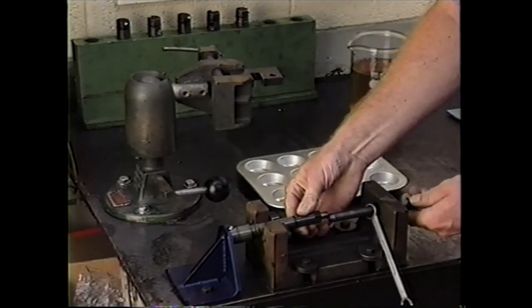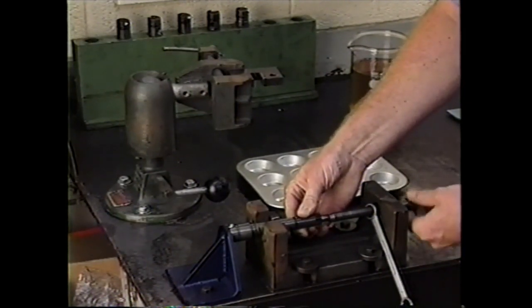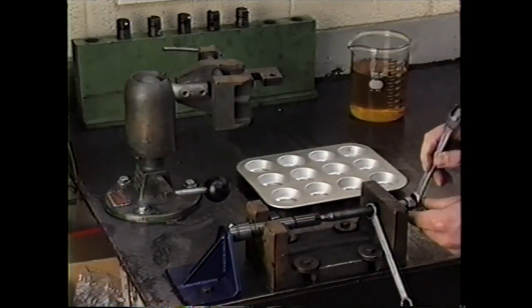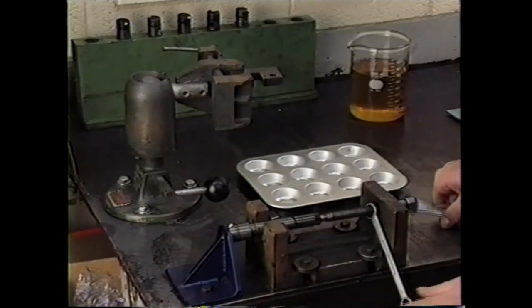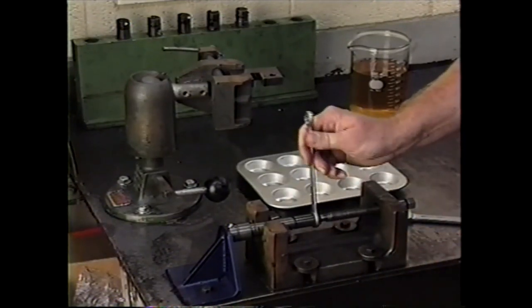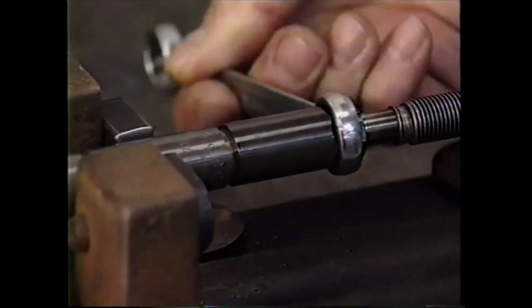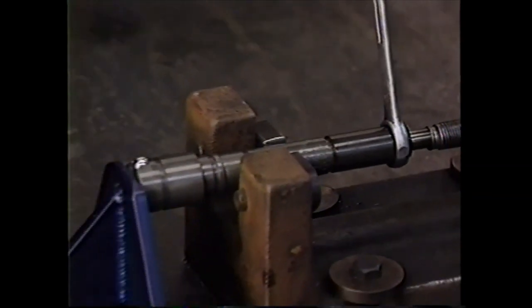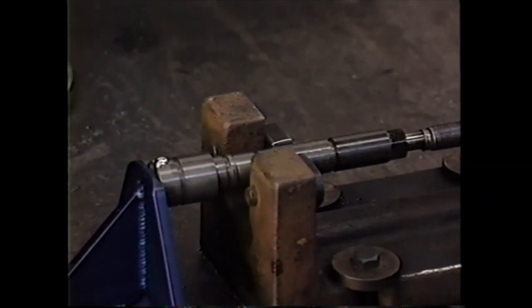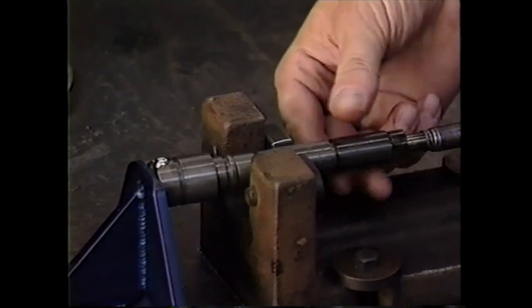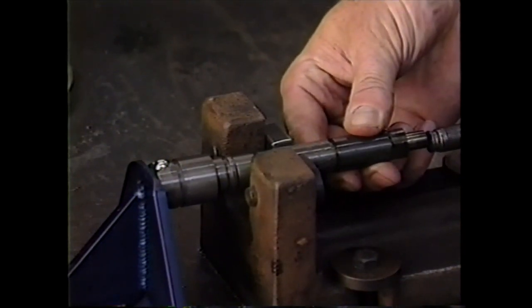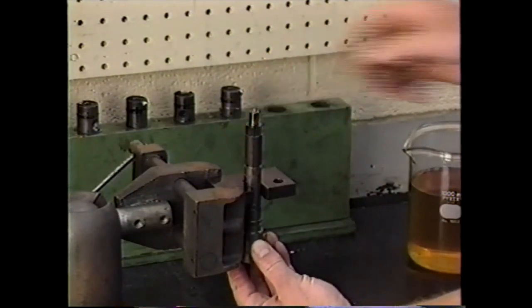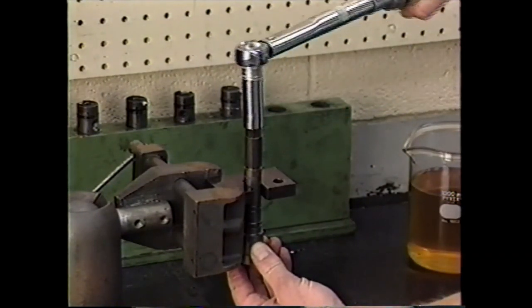Again, relieve the spring pressure on the nozzle tip by clamping it to the nozzle body. Tighten the nozzle nut until it's snug. Do not tighten the nut fully. When you feel the turning resistance increase substantially, remove the nozzle from the clamping tool and install it in the proper fixture. Then, torque the nozzle nut to specification.